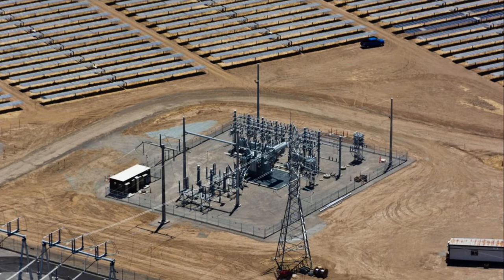And there may not be a grounding conductor at that point, because they may have the neutral. If it's a 4-wire, they may have a neutral, and that neutral is going to be connected to ground at their substation and all, but they may dictate where that connection is made at a service at medium voltage. So the medium voltage services are very, very different than low voltage services that we have for buildings. And so we just go to their guidelines and their rules and we follow those.